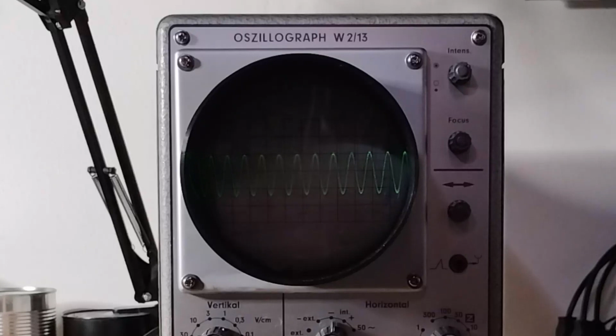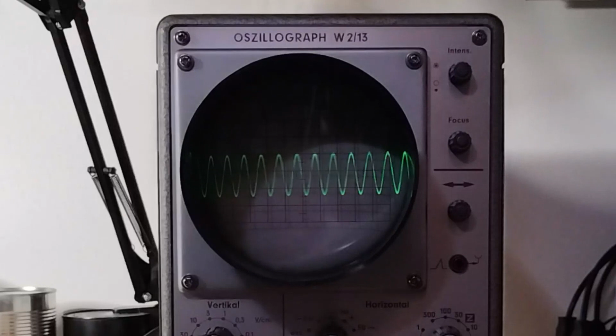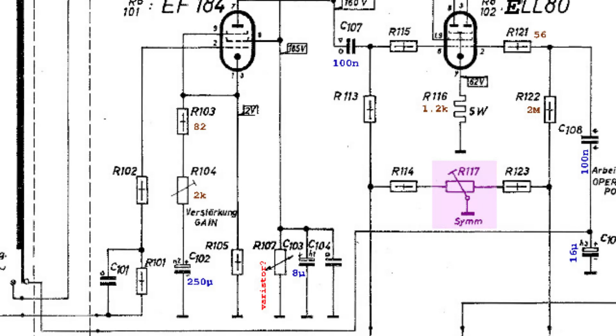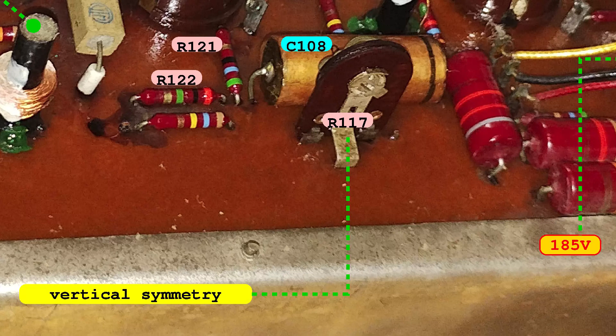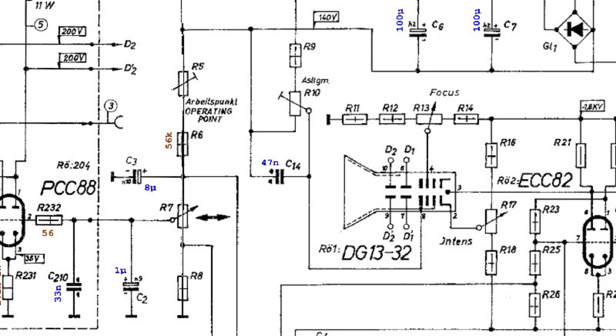Vertical calibration and symmetry. Instead of using the calibration signal to calibrate the vertical scale to the reticle that is printed on the plastic screen before the CRT, apply a sine wave signal from a reliable source generator, knowing what would be the expected height in centimeters, and the trimmer resistor R104 could be adjusted accordingly. The trimmer resistor R117 could then be used to fix a possible asymmetry between the upper and the lower part of the wave that is represented. Horizontal operating point. Like for the vertical operating point, there is also the possibility to set the horizontal operating point if the potentiometer R7 is not in the condition to do its job correctly. For this, the trimmer resistor R5 can be used.